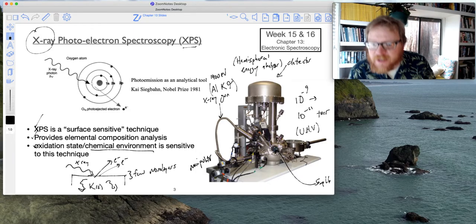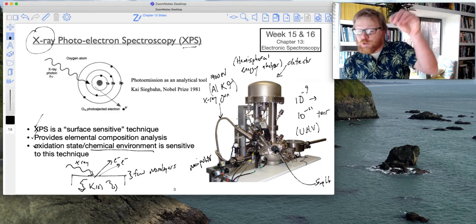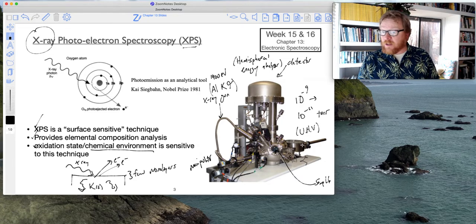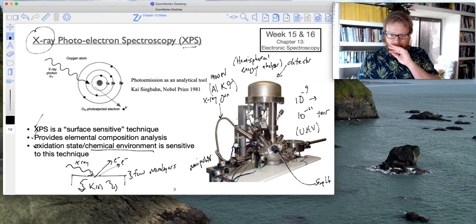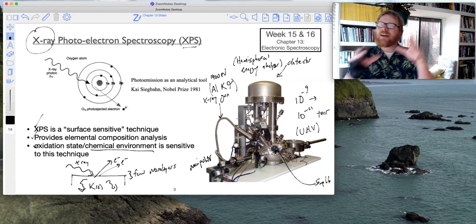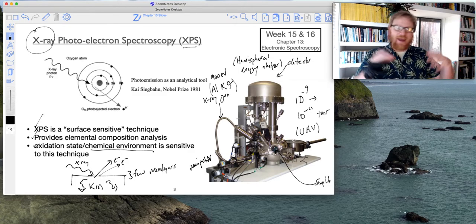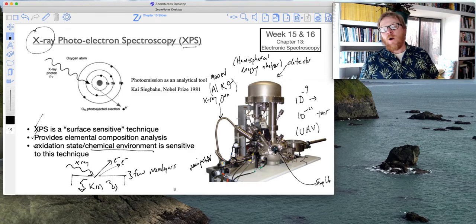So you can see in this device, this little hatch would be opened up so you could place your sample on a little robot arm, and that robot arm will close up, seal everything, just like the International Space Station has a load lock and the main chamber, right? The main space station chamber where everybody lives. Well, that's exactly how these types of vacuum systems work.